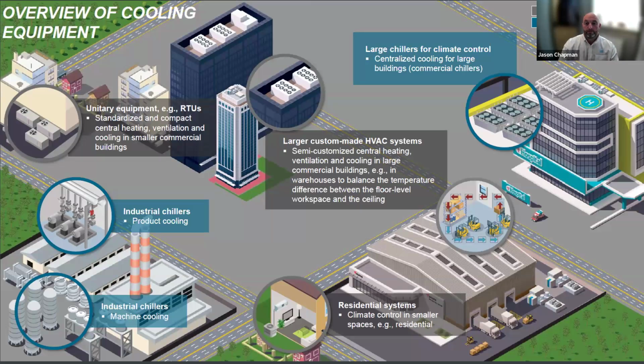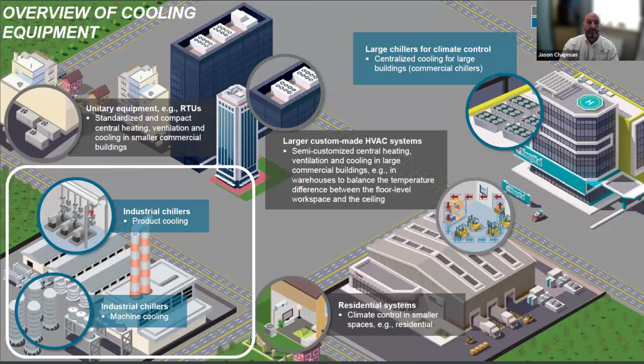Commonly, the largest systems will have HVAC systems, residential systems, unitary equipment for RTUs and standardization of components and things like that, and also large chillers for climate control. So as you can see on your screen there, we have circled the ones that fall into process cooling. And to be a little bit more specific, the area that's been highlighted in the white box there is where we're looking at on the process cooling side of things. So we're not discussing HVAC, residential cooling, comfort cooling, or room ventilation of any type. It's purely down to production and industrial cooling of a process.